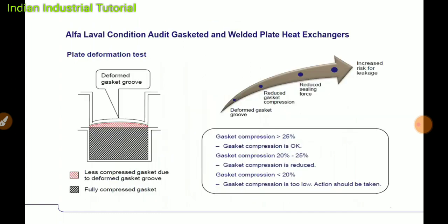This plate groove deformation is repaired at our service center. You will notice this plate deformation at site also. But if it is less than 20%, we allow this gasket deformation to use. But if it is more than 25%, then we say that it is to be sent to service center for repair.